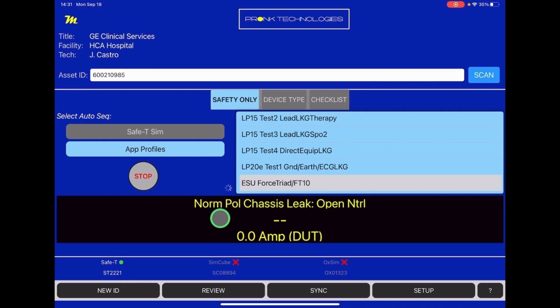You can see here it's going on to the next test, which is doing a chassis leakage test, but with the open neutral. That is why the ESU powered off, because the service manual requires us to do the chassis leakage test with the neutral line open, so the Safe-T Sim automatically opens up that neutral line for us to run that test and collect that result. So it's normal for the ESU to power off after that test, so nothing wrong because it does that. So we're going to let it continue and finish the testing that's required so we can capture all this information.